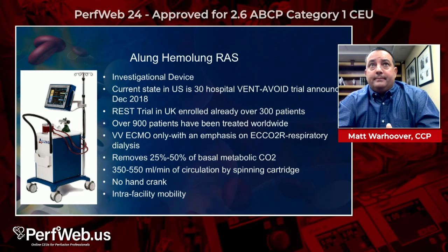It's been used in multiple different places across Europe and Asia, and they did one of the largest studies of this in the UK, and it really eliminates the surface area on this device. It's very low impact, and because it's almost like a CRRT machine, you don't have to anticoagulate fully. It's a very unique, kind of a niche product for your CO2 retainers. No hand cranks available. You can do intra-facility mobility, but not extra-facility, because it does have a very short battery life, and as you can see in the picture, it's a large piece of equipment that's just not going to transport very easily if you have to go from facility to facility. Next slide.